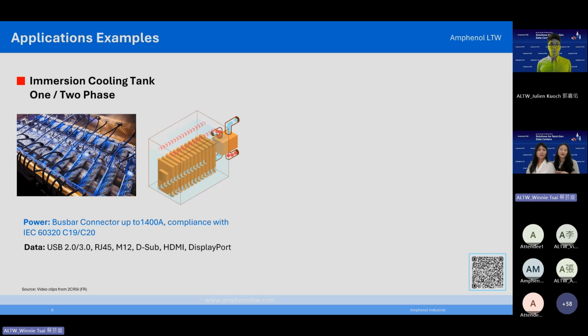There are two types, single phase and two phase. Single phase is simple: you fully submerge the server, the coolant carries the heat to a heat exchanger, and cool liquid comes back in. Two phase is clever: the fluid boils at a low temperature, around 50 to 60 Celsius degrees, and the vapor carries the heat away, then it condenses and drips back, so it's clean and efficient.